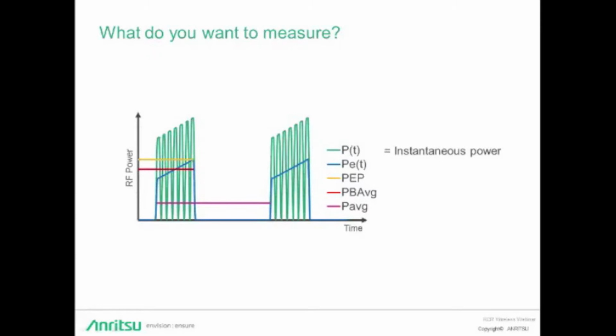When we're measuring RF, you want to talk about the different types of power measurement terms that you might hear. If you're looking for instantaneous power, you want the sensor to operate the diode in the linear region. However, the ability to track the power will depend on how quickly the sensor can charge and discharge the capacitor. Even though diode sensors react much faster than thermal sensors, they may not be fast enough to recreate the waveform. In those cases, you probably want to use a high-speed digitizer or a DSO oscilloscope, as we mentioned in a previous slide. So in many cases, engineers are interested in what we call the peak of the envelope power, which is the amplitude change due to the modulation or distortion. Again, the diode should be in the linear region, and its effectiveness to capture the peak power envelope will depend on the rate of change of the envelope.